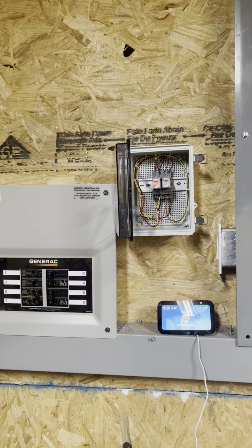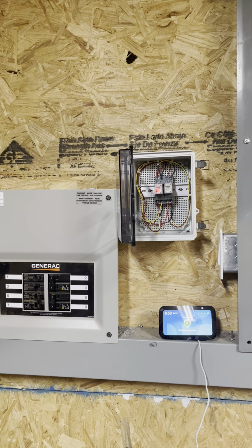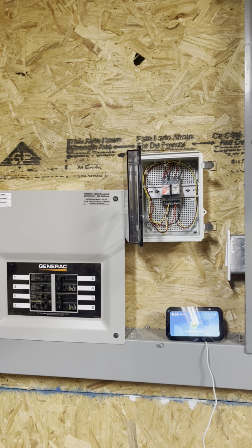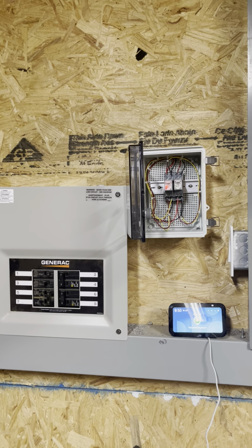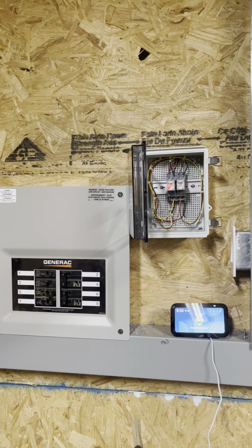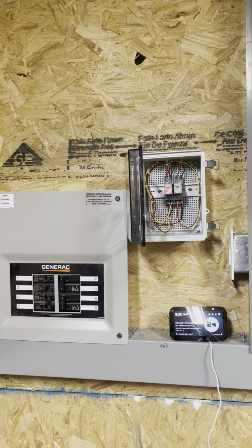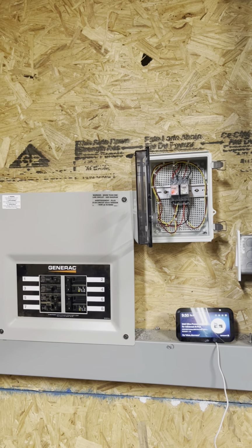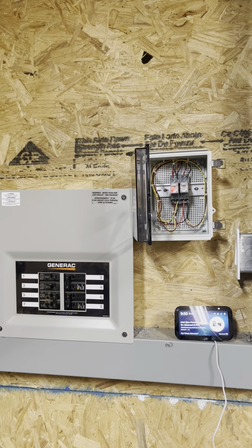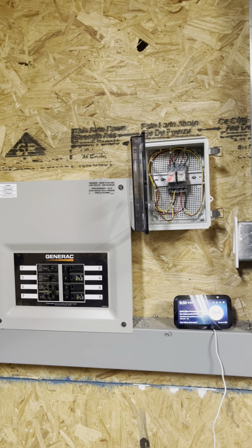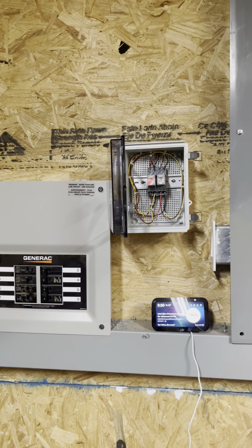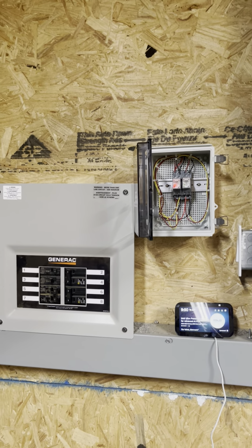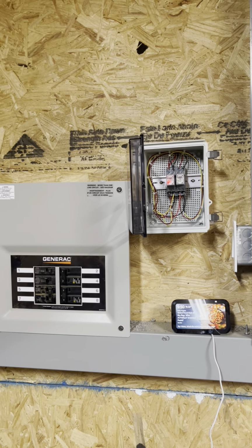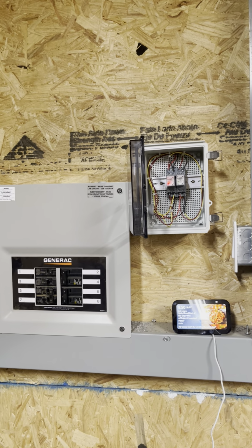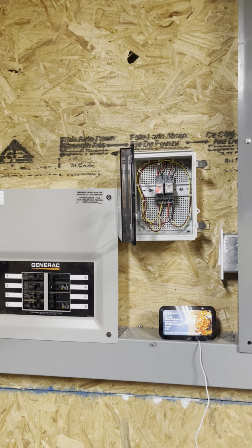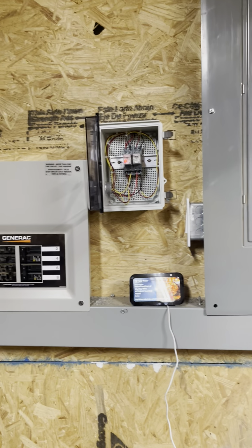So I let the inverters, which have the ability to supplement the generator with battery power for those peaks, do their job. And so I will bring in about 25 amps of power out of the 30 that the generator is capable of producing, and I will feed it into the system. It will use it where it's needed, but it'll also put it back into charging the batteries.